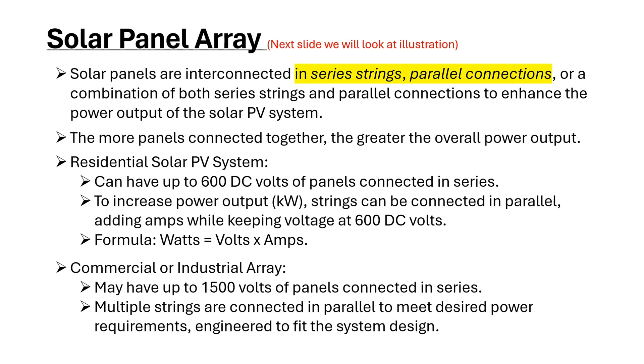There are basically two ways to connect panels: series and parallel, or a combination of both. The more panels you connect, the greater the overall power output. Remember: watts equals volts times amps. For residential solar PV systems, you can have up to 600 volts DC with panels connected in series. Strings can then be connected in parallel to increase output, adding the amps while keeping the volts the same. In commercial and industrial applications, it may go up to 1500 volts, with multiple strings connected in parallel to meet the desired power requirement.